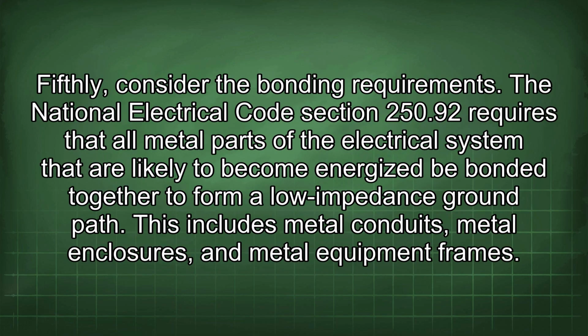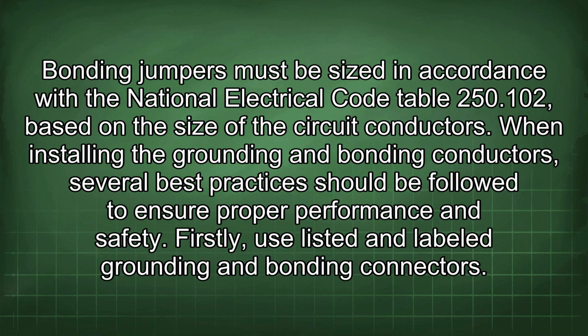Fifthly, consider the bonding requirements. The National Electrical Code Section 250.92 requires that all metal parts of the electrical system that are likely to become energized be bonded together to form a low-impedance ground path. This includes metal conduits, metal enclosures, and metal equipment frames. Bonding jumpers must be sized in accordance with the National Electrical Code Table 250.102, based on the size of the circuit conductors.